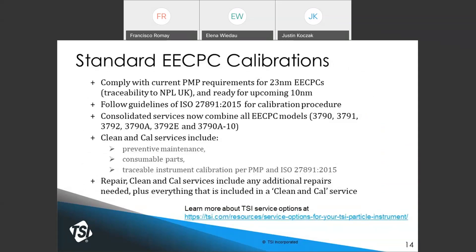The standard EECPC calibrations are applicable for either 23 or 10 nanometers. An important point: when TSI receives a CPC for calibration, preventive maintenance is performed first — cleaning nozzles and orifices, replacing internal filters, changing the wick, and cleaning the optics — to ensure the instrument is performing well before calibration.